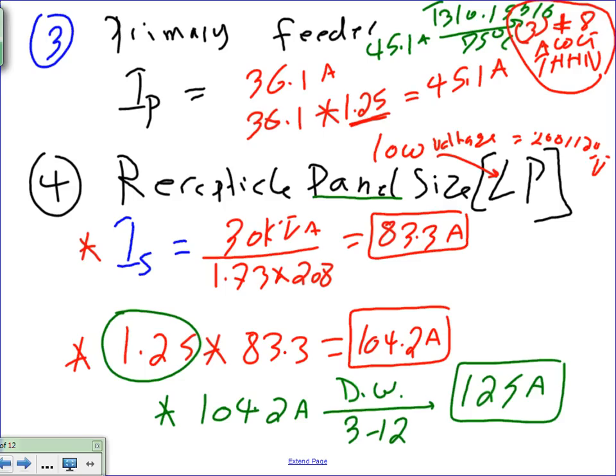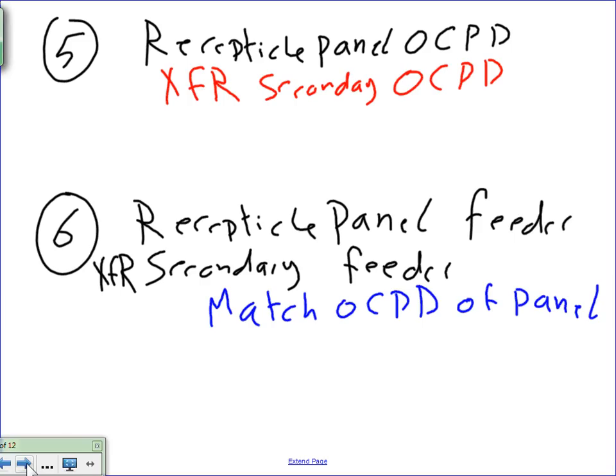Okay. This is what you guys are going to be doing for me in the project when you size the receptacle transformer. Can I move? Yeah. All right. Now the fourth thing that we need to size, the receptacle panel overcurrent protection device. Now this one is the receptacle panel overcurrent protection device, and Nick, the same device is actually also the overcurrent protection device for the transformer, right?